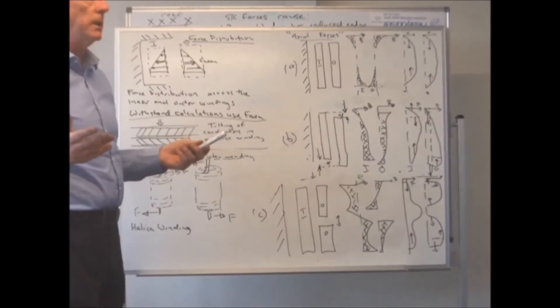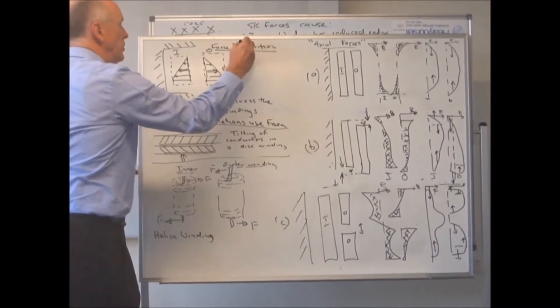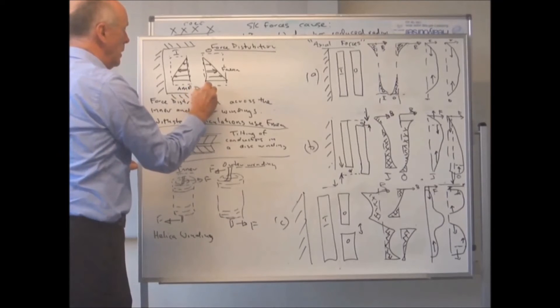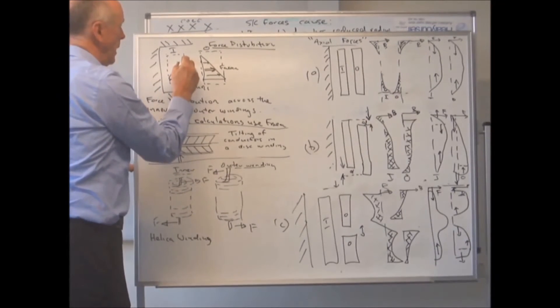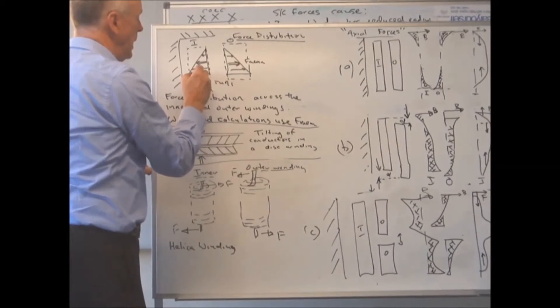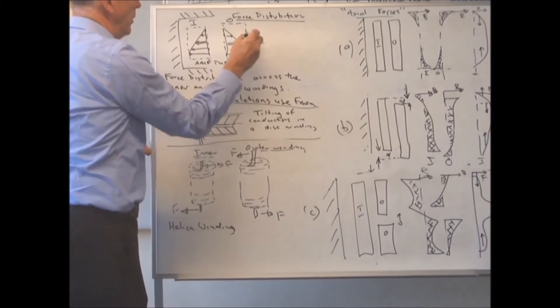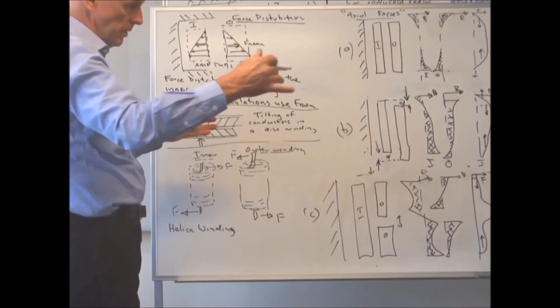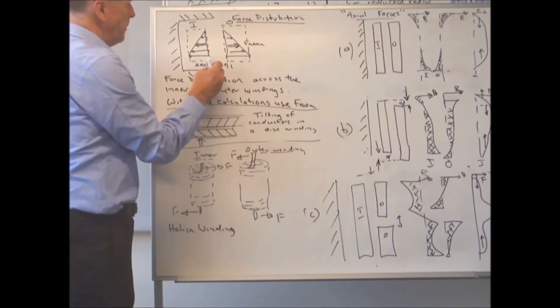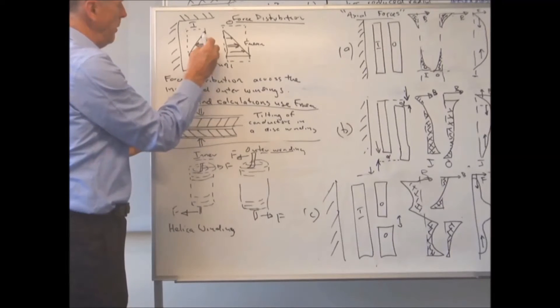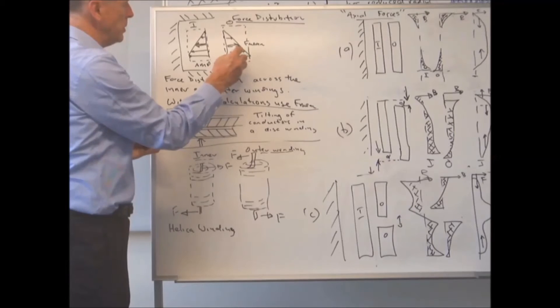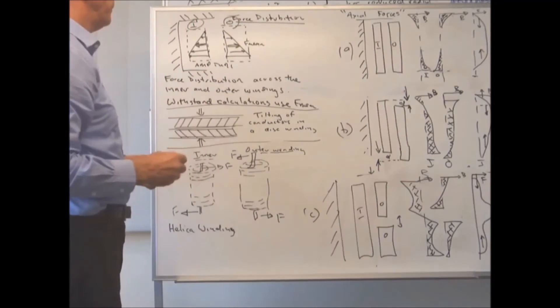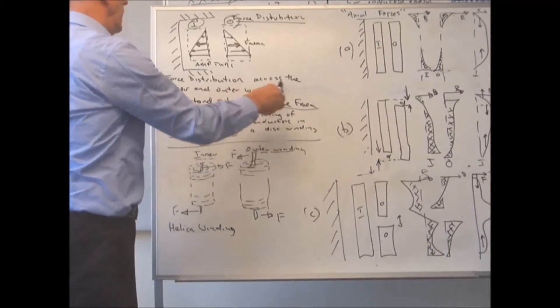Before going into more detail: the force distribution in the winding varies with the ampere-turns. As you move from the outer to the inner winding, the ampere-turns increase, and on the outer winding they also increase. So the force actually varies with the ampere-turns as the current increases in the field. We assume the mean force — working with the mean between the minimum and maximum — in terms of compression for the inner winding and expansion for the outer winding.